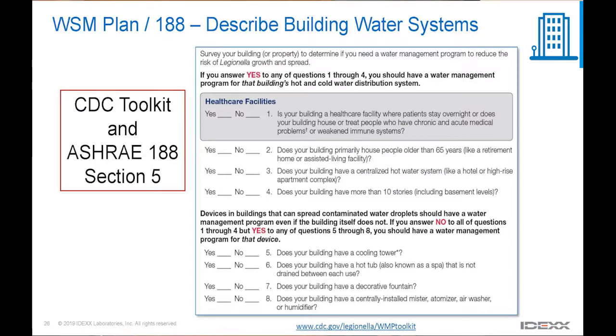Check that—you have to have a water management plan for the cooling tower, not necessarily for the whole building. If you're not a healthcare facility, say a four-story library or bank downtown, without a centralized hot water system or any of the other characteristics, you don't need a water management plan for your potable systems, but you do for that cooling tower, because cooling towers are associated with outbreaks.